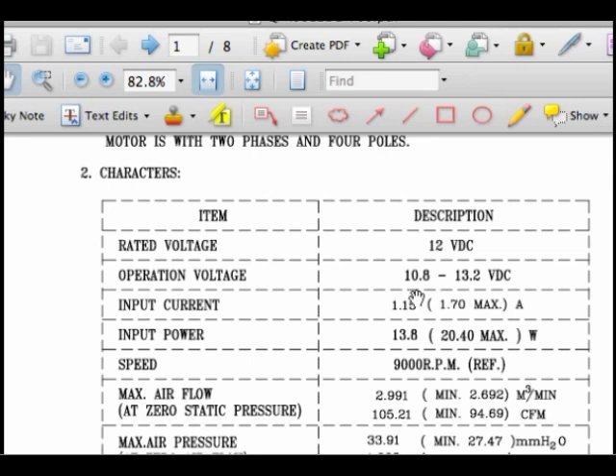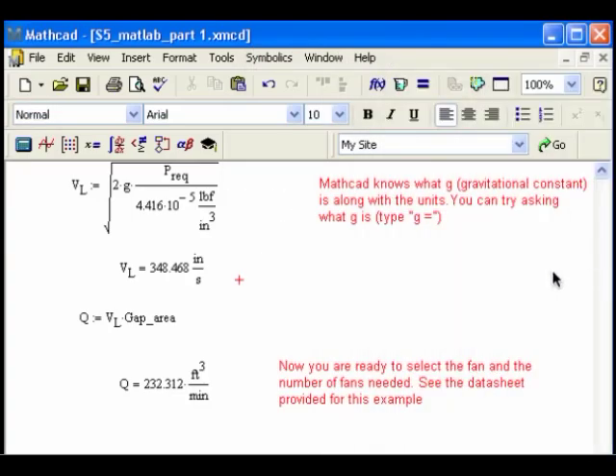So 1.15 is the nominal current. Now, it may not actually draw that much. It's actually telling you 1.7. If you looked at the fan, it will say 1.7 on the fan, but this case is actually telling you the nominal, so it's telling you that 1.15 is really what it will probably draw. So stamped on the fan is 1.7, but in reality, if you test it, it will probably draw 1.15. So 1.15 amps, I'm going to need that, because I have three of those fans, so I need to know how many amps I'm going to draw.